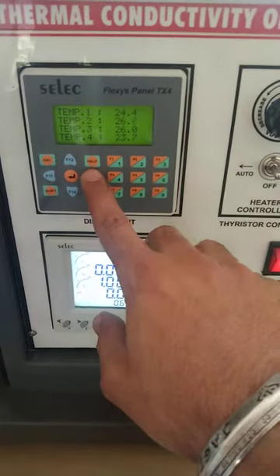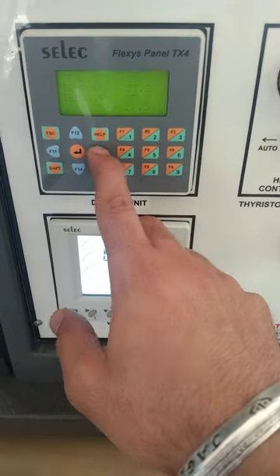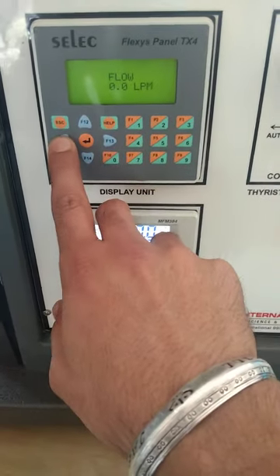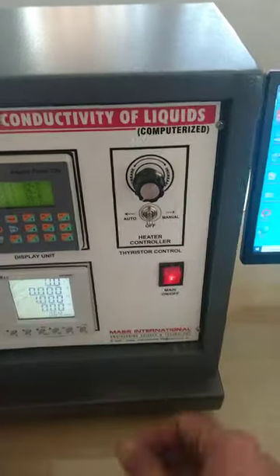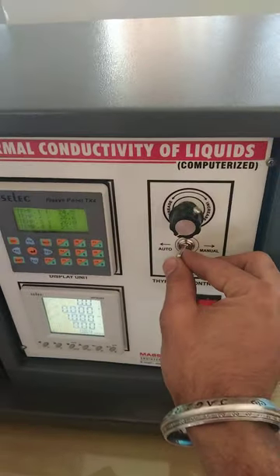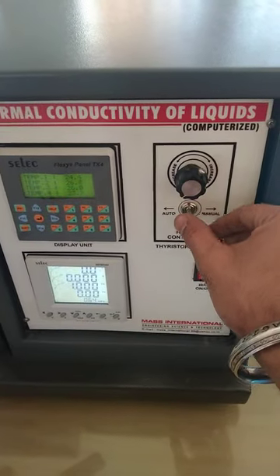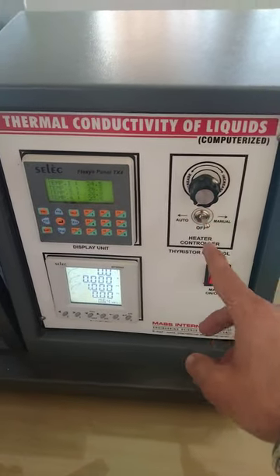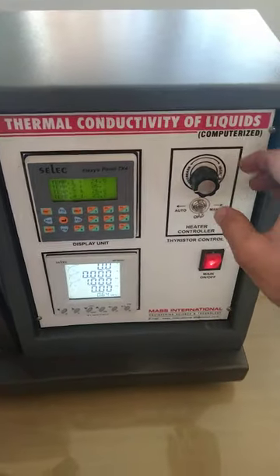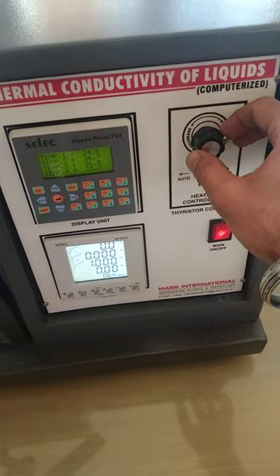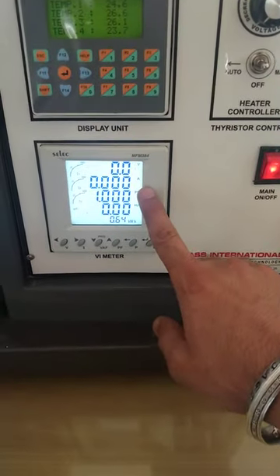These are the temperature readings — all temperatures are shown up to temperature T8, and there is a flow rate reading. Here is the auto as well as manual switch. In auto mode, readings are displayed directly on the computer software; in manual mode, all readings are displayed on the PLC. This is the voltage-increasing knob — we have to regulate the voltage from this knob. This is the voltmeter as well as the ammeter reading.